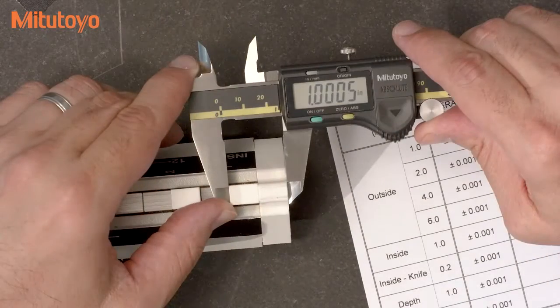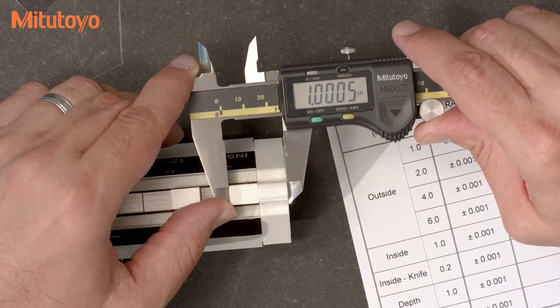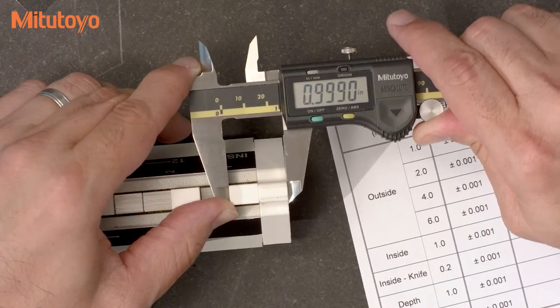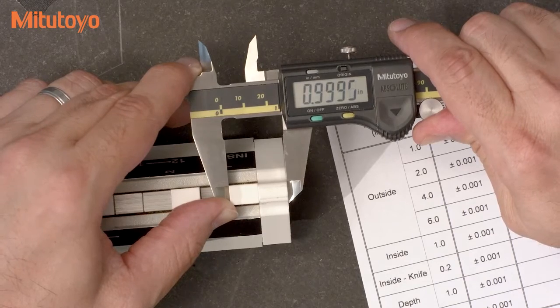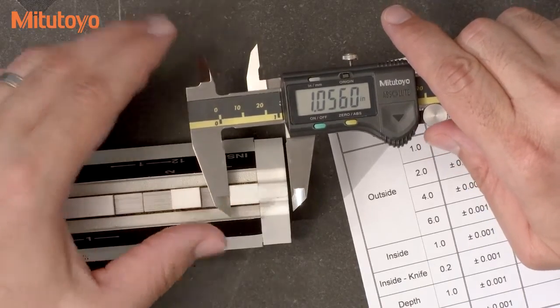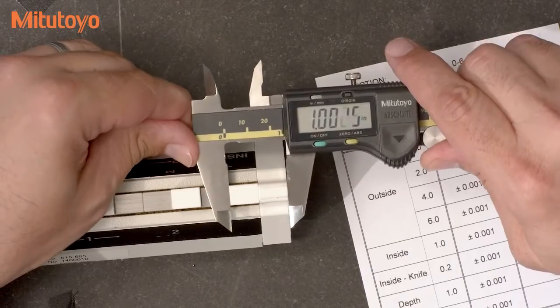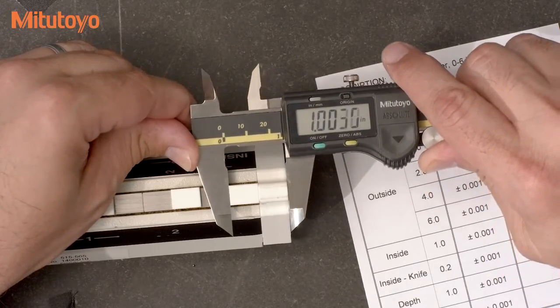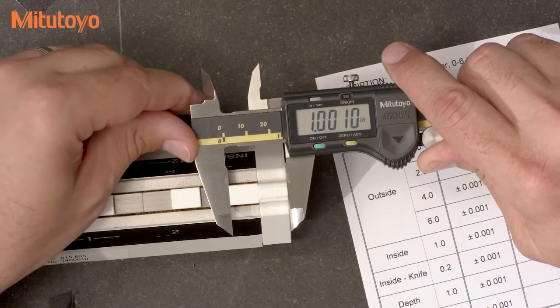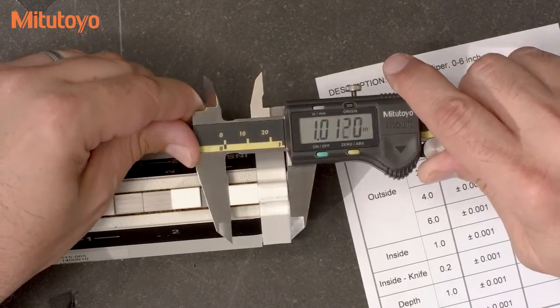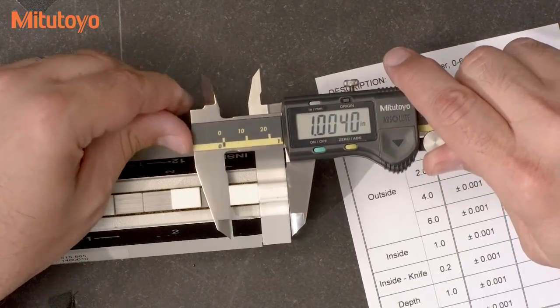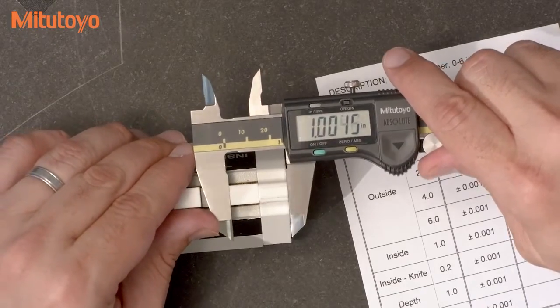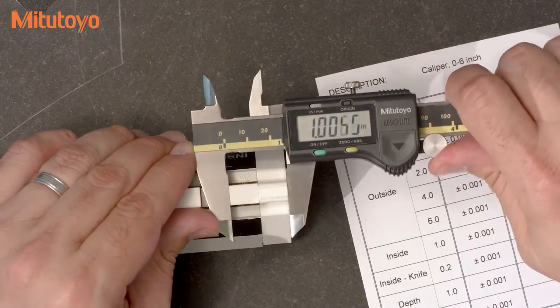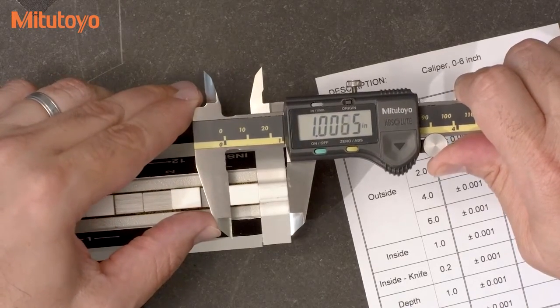When using or calibrating a caliper, it's important to learn how to get a consistent value. The amount of force you apply can vary the results. As you see here, I am applying too much force, and the values change by several thousandths of an inch. So don't do that. Alignment is also a problem. If you're misaligned in this direction, you can see the values get larger. If you are misaligned in this direction, again, the values get larger. So you want to rock the caliper in both directions while applying a consistent force and looking for the smallest value.